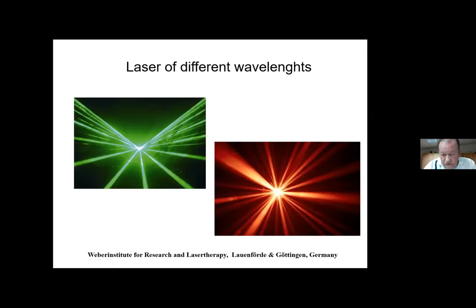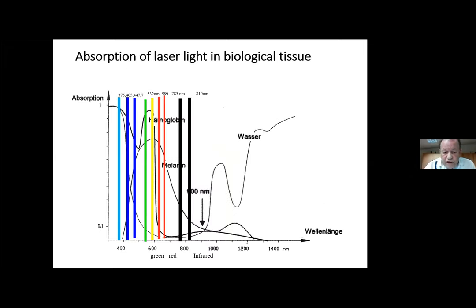We use different lasers of different wavelengths across the full spectrum of light — from UV through blue, green, yellow, red, and infrared. The available lasers we use include ultraviolet at 375 nm, blue at 405 and 447 nm, green at 532 nm, yellow at 589 nm, red at 632 and 660 nm, and infrared at 785 or 810 nm. We have a very good supplier who can make any new wavelength we need. This is very important because different substances have different absorption spectra, and we must use the right wavelength for maximum absorption and excitation to get a good quantum yield of oxygen radicals.